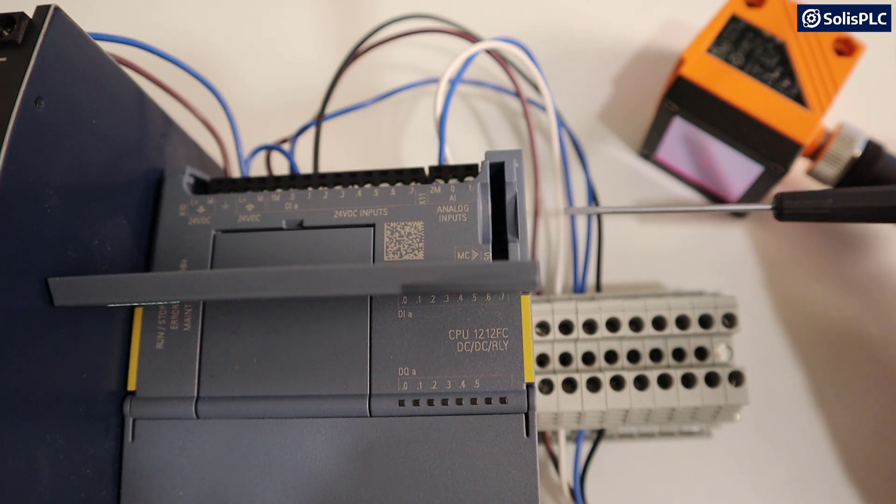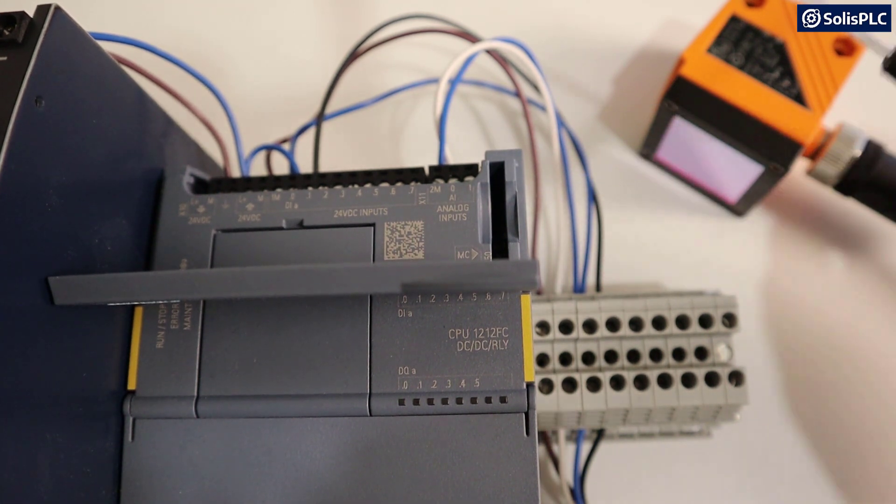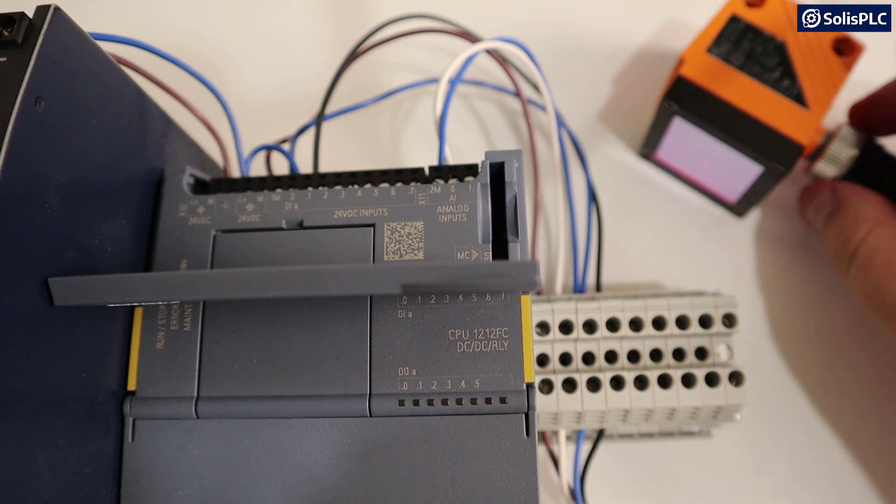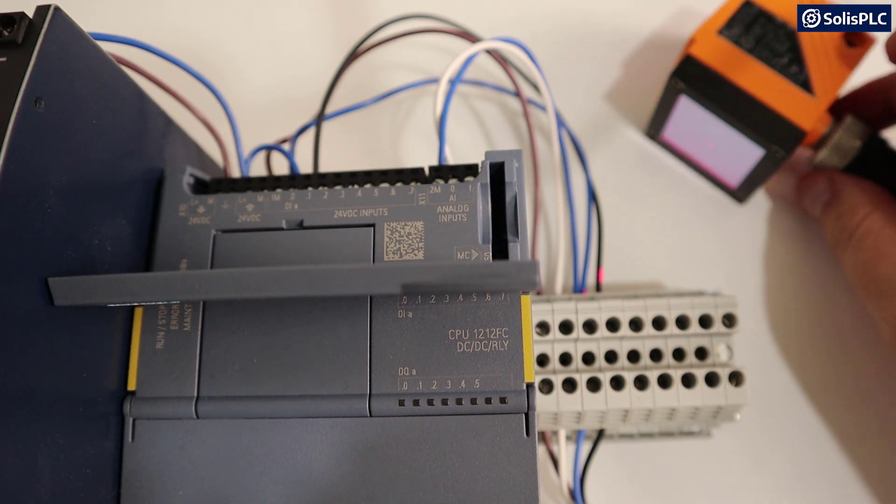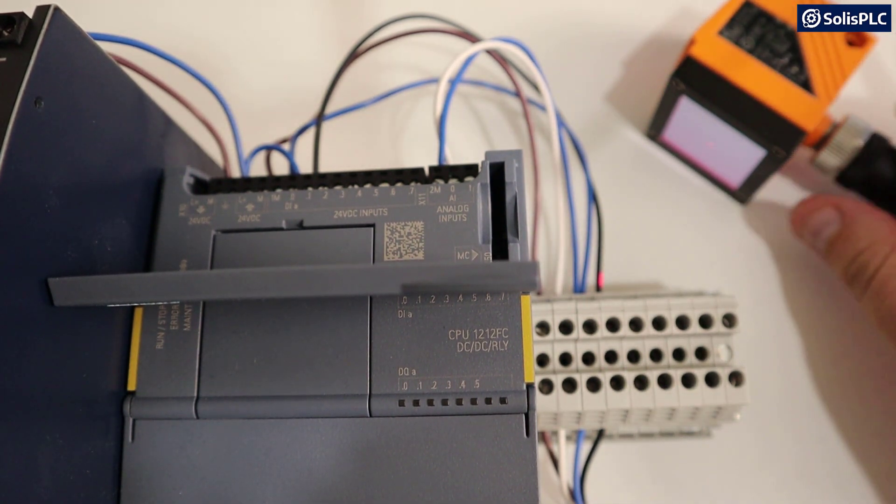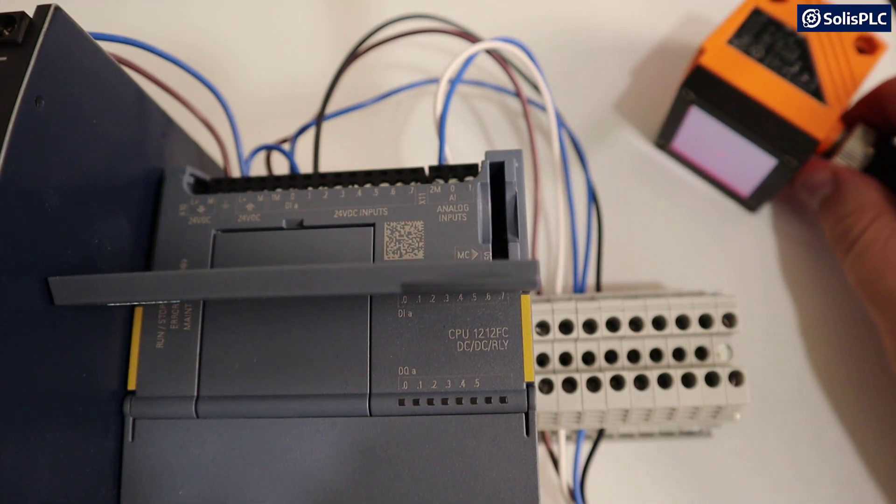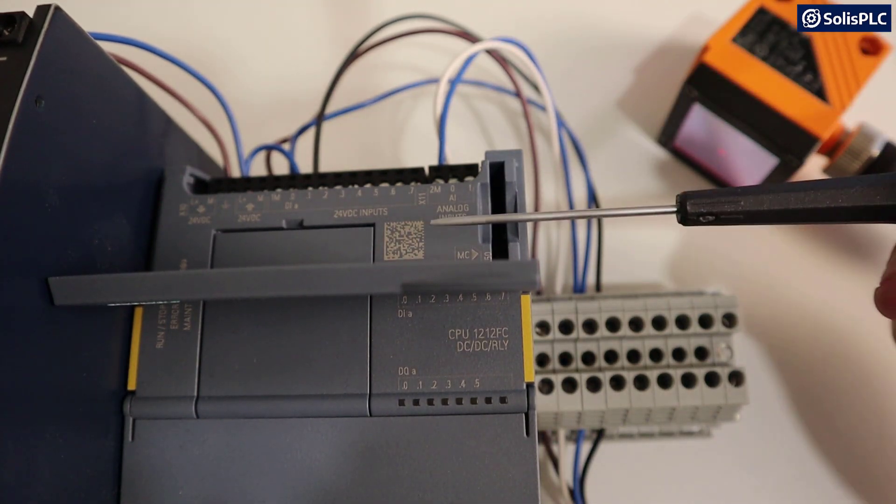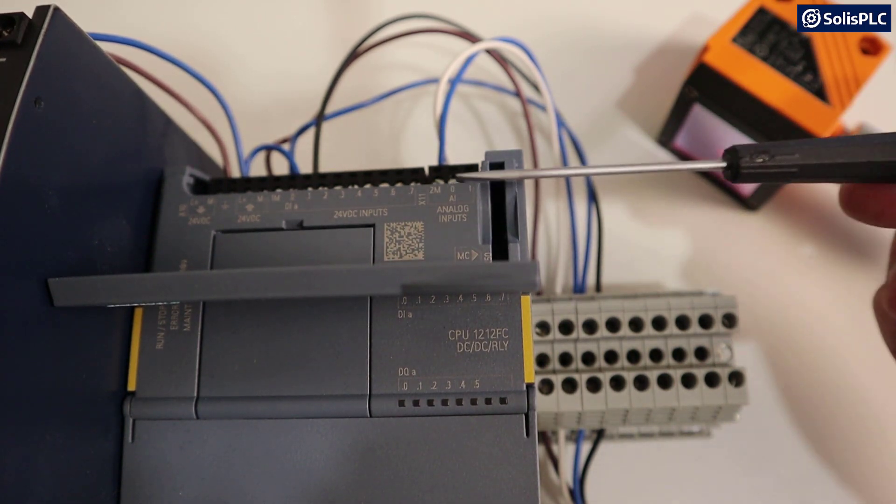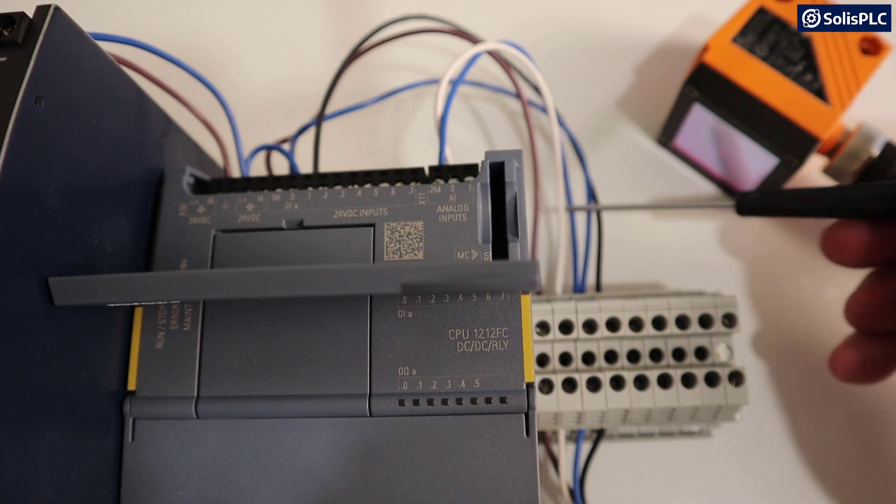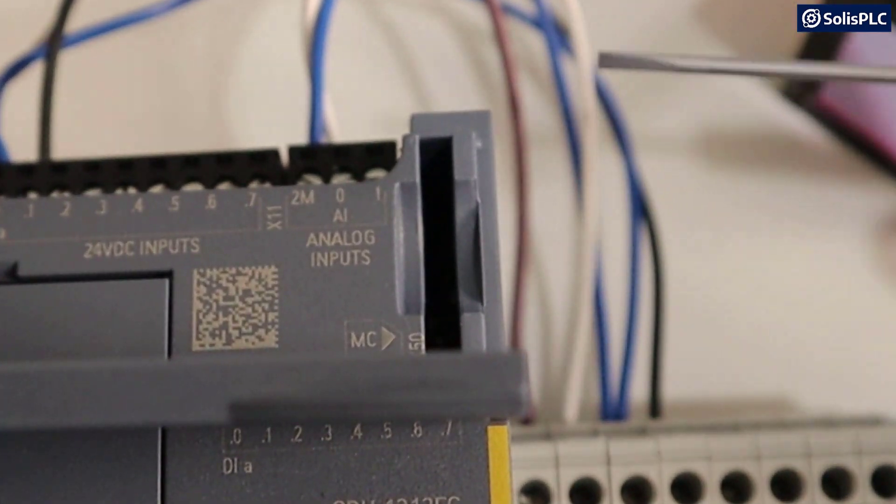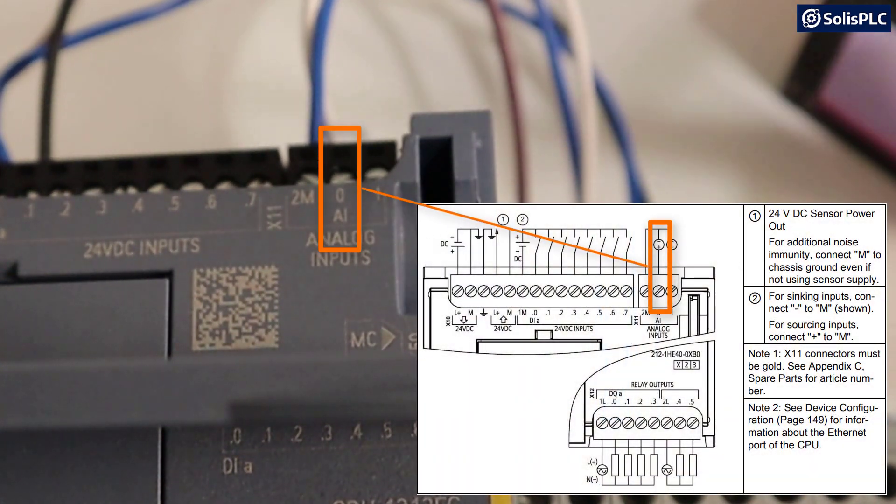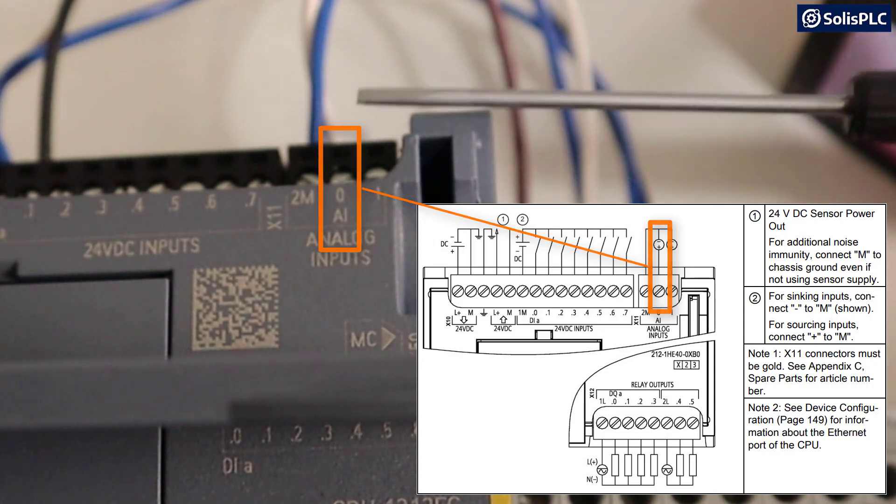However, we are using output number two of the sensor, which provides an analog 0 to 10 volt signal that's going to correlate to the distance from the sensor to the object. Now, we're not going to go into too much detail as to how to set up the sensor because our focus is on getting that data to the PLC. But what you need to know is that we've connected the analog output, which is currently on this white wire to analog input number 0 on our SIMATIC S7-1200 CPU.